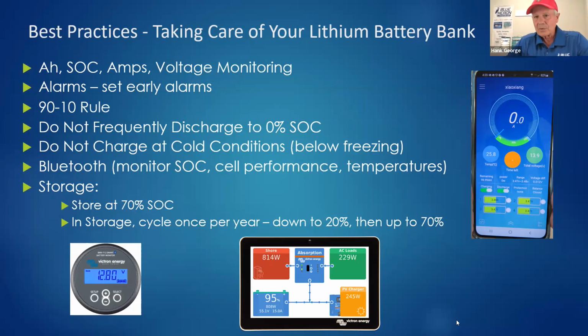You don't want to frequently discharge to 0% state of charge. In cold conditions, freezing water temperature is a pretty good reference. You don't want the temperature at the battery bank to be getting below 32 degrees and then try charging at that point. If it's in storage, it's fine, it's not a problem. The issue is charging. And in fact, you can discharge.